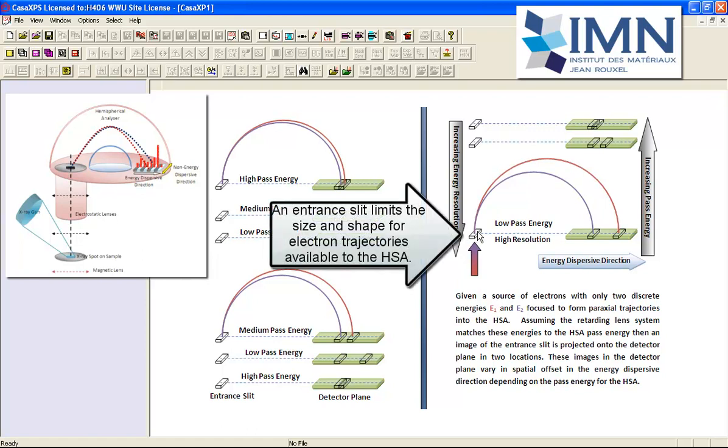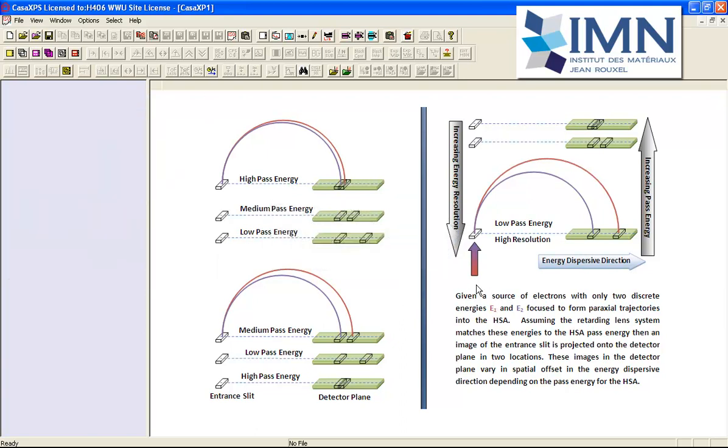We can understand this in the context of the hemispherical analyzer and the information that is entering the hemispherical analyzer through an entrance slit. If we had an ideal experiment where we had electrons entering in a paraxial way into this entrance slit and they only arrive with two different energies, E1 and E2, where E1 is greater than E2.